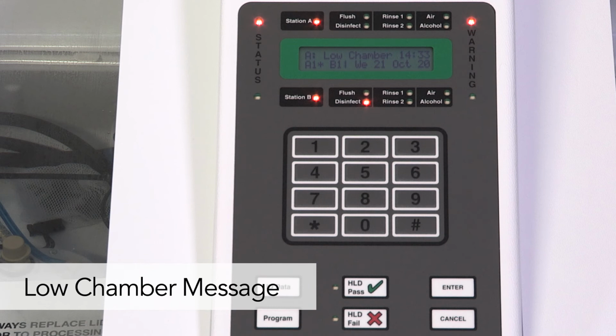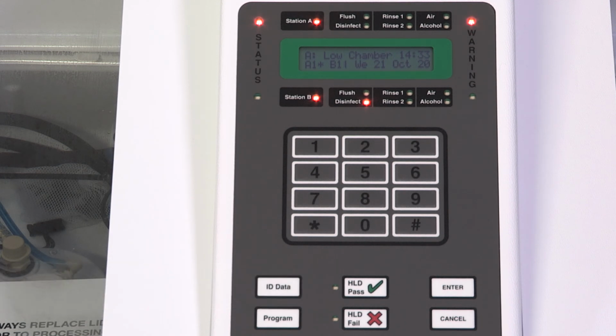If the basin fails to fill to a certain level in the required time, the unit will stop, alarm, and the status and warning lights will flash. The display shows low chamber. Check the cycle phase indicators on the control panel. If the unit alarmed in the rinse cycle, there is a water problem.